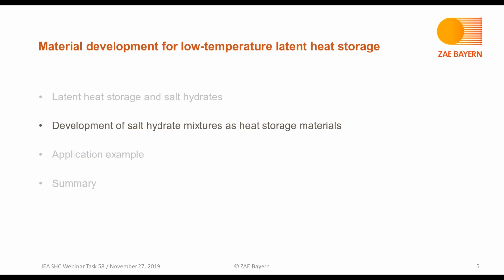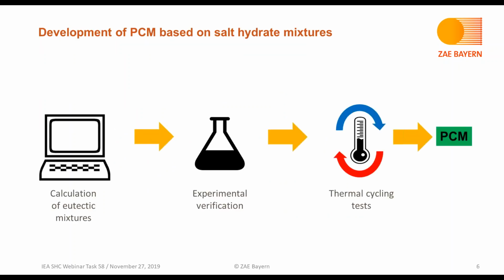So how does it look like to develop salt hydrate mixtures as latent heat storage materials? In our case, we were following this line of development. In the first step, we calculate mixtures to identify eutectic mixtures. I will show you later why we are doing this. After the calculation, the predicted eutectic composition needs to be experimentally verified. If this verification is successful, we perform thermal cycling tests to test the material under application conditions. And if these tests are also successful, then we have developed a new PCM.